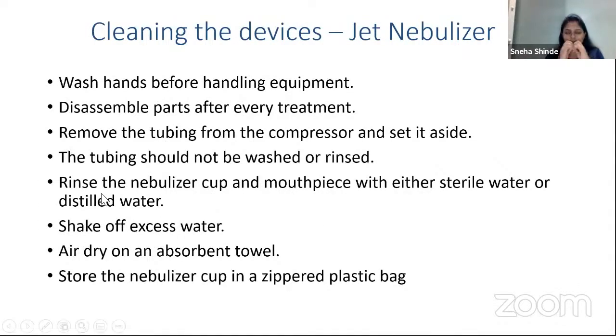This step is very, very important, and it is always neglected: after each use we have to clean the mouthpiece and the nebulizer cup with sterile water or distilled water. Why? Because there is always some residual present in the nebulizer cup after each nebulization. If it remains in that cup, there are high chances of pathogens growing in that chamber. For respiratory patients, that is the worst which can happen. So we have to always clean the nebulizer chamber after every use.